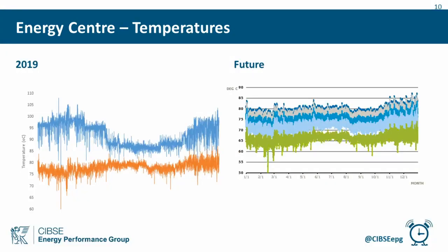One of the challenges we have with Citigen is it supplies old buildings in the City of London. As a result, our supply temperatures are high, as are our return temperatures, as Phil mentioned in his presentation. In order to get our efficiency up on our heat pump, we need to do something to bring down those return temperatures.